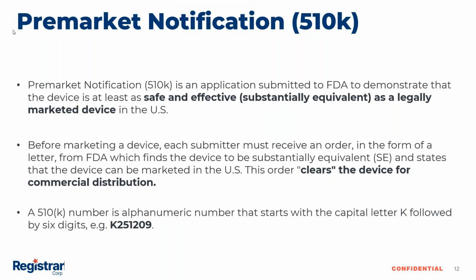That is also the big difference between a pre-market approval and a 510K. A pre-market approval often includes clinical trials and data. That is not the case here. I mean, you can use them, it's not forbidden, but it is not really required. As long as you can provide that information and show with data that your device is at least as safe and effective. It might be better than something that is on the market, but it needs to be at least safe and effective. So you really need to compare your device with something that is on the market.